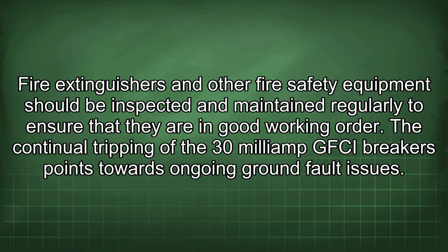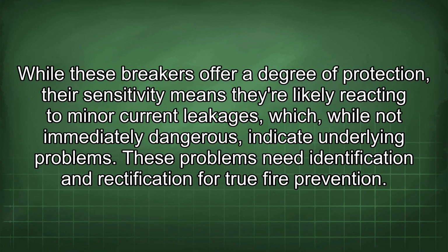The continual tripping of the 30 mA GFCI breakers points towards ongoing ground fault issues. While these breakers offer a degree of protection, their sensitivity means they are likely reacting to minor current leakages which, while not immediately dangerous, indicate underlying problems. These problems need identification and rectification for true fire prevention.